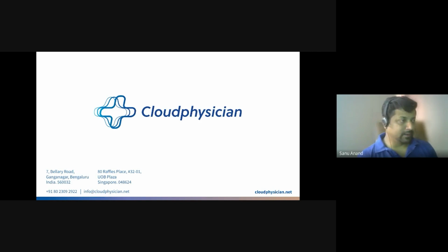What we routinely do, if anyone has worked in a cardiac unit, we call in patients for what we call pacemaker interrogation regularly, and the device will check if everything is working fine, and if it's not working fine, it'll spit out a report, and based on the report you can easily reprogram this, and it can be done bedside pretty easily these days. So we don't place a magnet to shut off the pacemaker any longer, but we do use a magnetic device to reprogram permanent pacemakers. Temporary pacemakers, there's no such thing. All the controls are external.